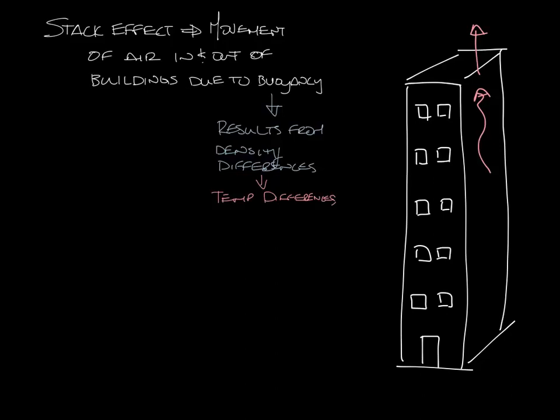Stairwells and elevator shafts contribute to the stack effect as hot air rises up them. The airflow leaving the top of the building creates a negative pressure that will draw air into the building. This air can come through doors, windows, and other cracks in the building. This is called infiltration, and the air leaving the building is called exfiltration.